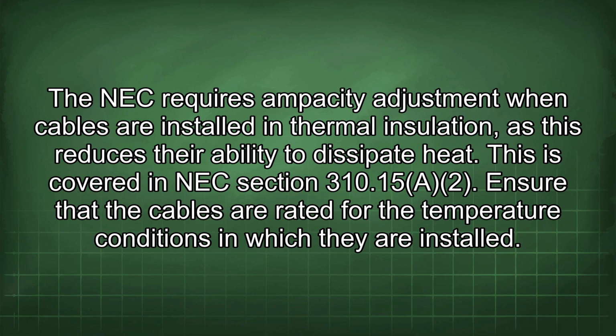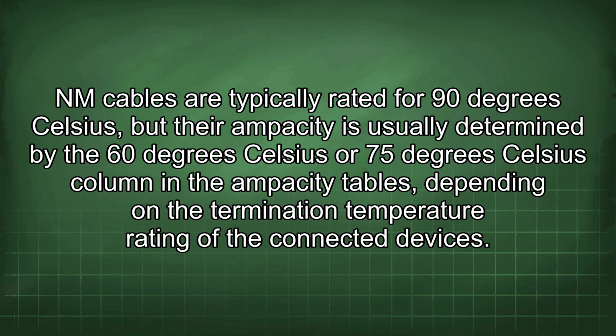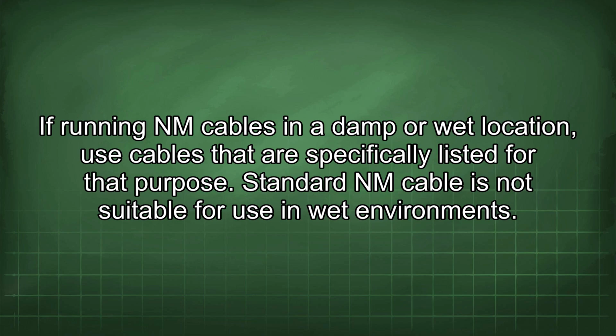Ensure that the cables are rated for the temperature conditions in which they are installed. NM cables are typically rated for 90 degrees Celsius, but their ampacity is usually determined by the 60 degrees Celsius or 75 degrees Celsius column in the ampacity tables, depending on the termination temperature rating of the connected devices. If running NM cables in a damp or wet location, use cables that are specifically listed for that purpose. Standard NM cable is not suitable for use in wet environments.